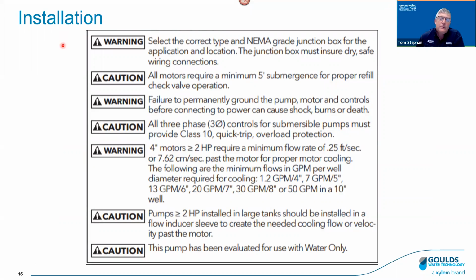Okay, installation. So there's an awful lot of stuff to talk about with submersible motors. And let's just hit a couple of these things here. Certainly grounding is required, right, by the NEC, also for safety purposes. This is a good reminder here saying that all three-phase pumps need overload protection, whether that's in your control box or your VFD, because they don't have built-in overload protection, you know, like some of your smaller single-phase motors.